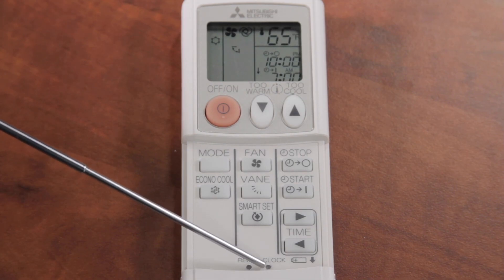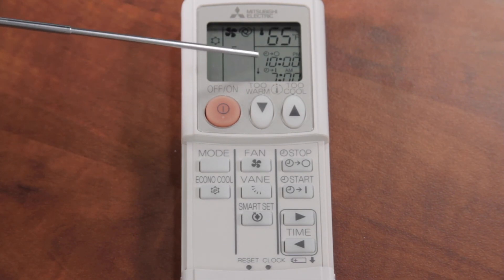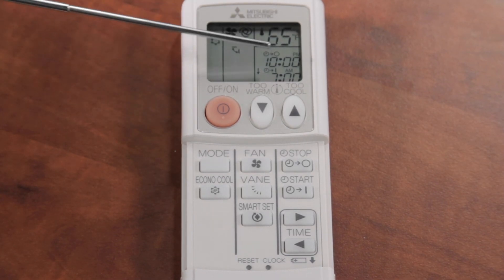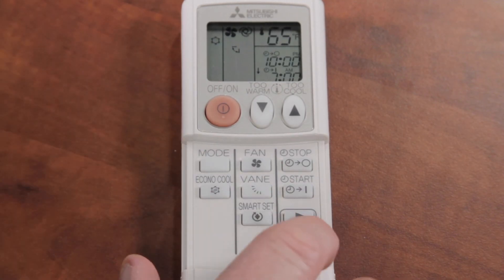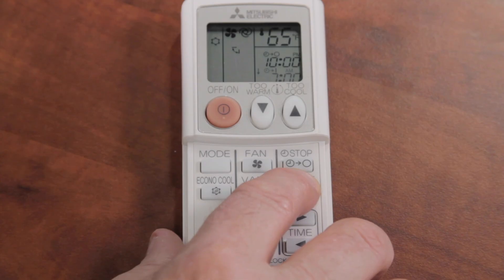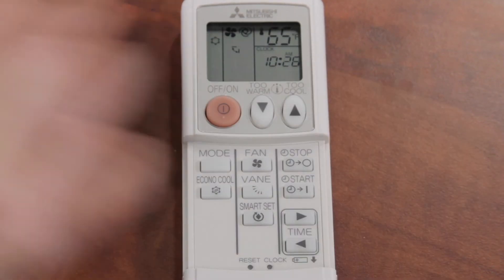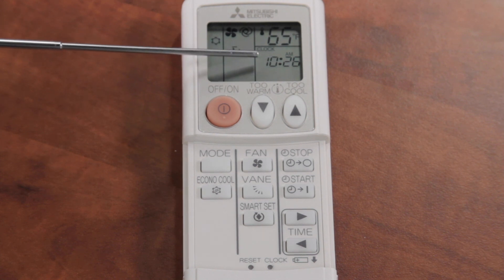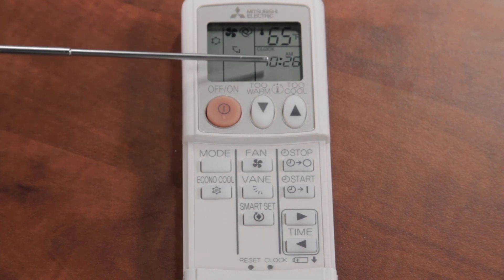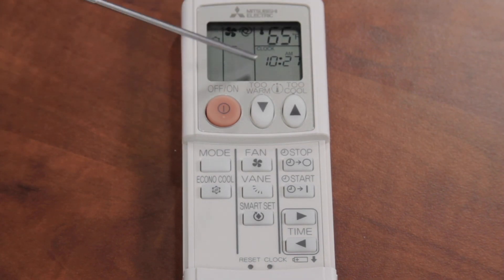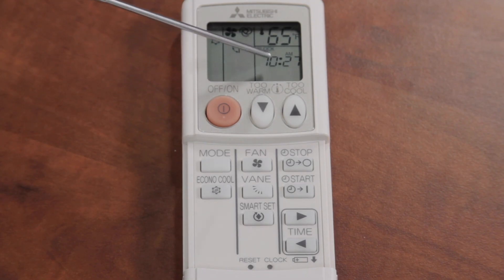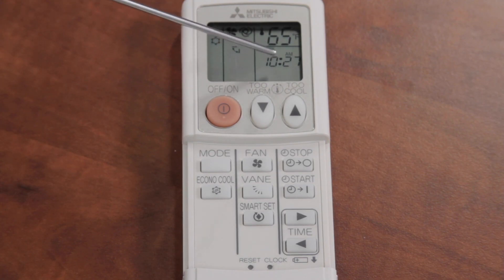There's one main thing I really want to bring out on this is that the clock needs to be set to the right time. A.M. and P.M. is on the clock. You cannot see the clock right now because the start and stop times have been replaced by that. To remove these start and stop times, all you have to do is press the start button. The start time went away. Press the stop time, and the stop time goes away. And now we're back to 10:26 a.m. and the clock is showing up again. The only thing I really want to stress is the importance of this time, that this clock is set to the right time. You're going to see there's an a.m. and then there's a p.m. Make sure that this clock is set right, because this is what's going to drive your start and stop time, this clock right here.